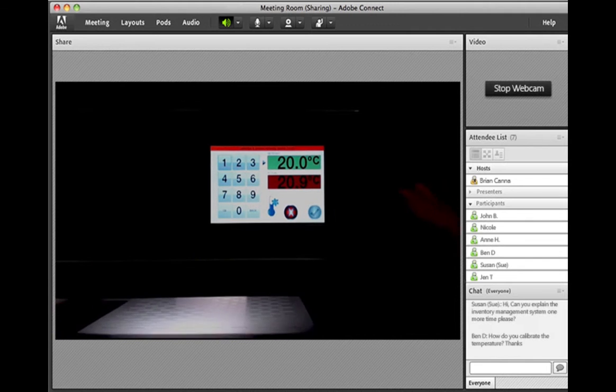We're not going to do that because it will screw up the current calibration right now, and this unit is calibrated, and I don't want to do that without a temperature sensor. But as you can see, it's moving down. This box will turn green when it's ready to take the measurement, and then you just actually enter here, hit check, and you will then calibrate the high side.